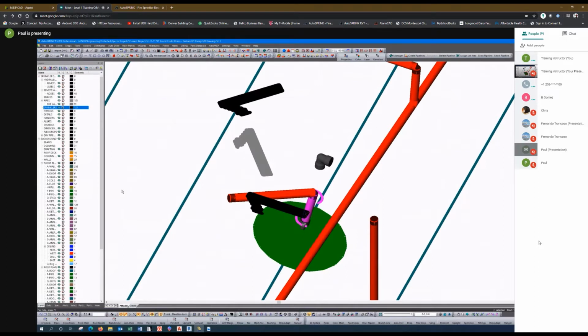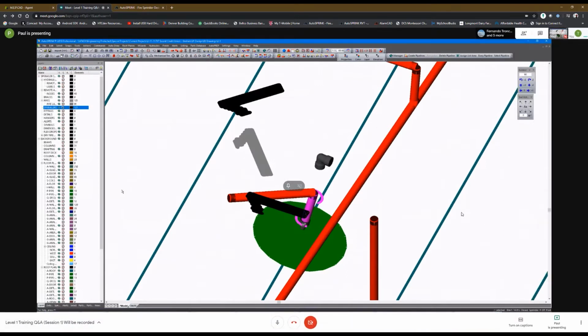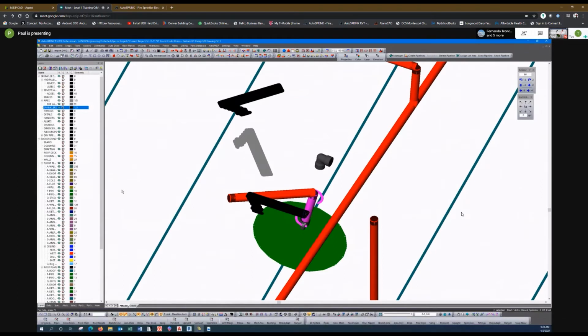Attaboy. I was hoping you can help me out on some standpipe design stuff. Possibly. Let's take a look at what you got going on. All right, we had a project here where we're swapping out the fire pump on an existing building. It was built back in 1987. The fire pump that we spec'd out from our fire pump specialist, Mr. Fred, he had stated that the pump might need to be a little bit bigger due to the fact that the city lost 10% of their static pressure at that location since the pump was designed back in '87. Understood. And I guess some requirements have changed as well.